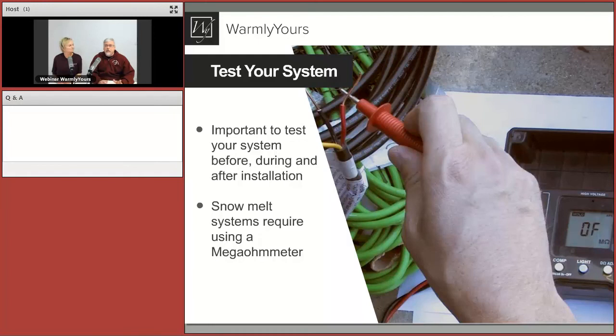This product requires a mega ohm meter for testing. It sends 500 or 1,000 volts down the wire to make sure the insulation is intact on the three wires — red, yellow, and black — that keep them from touching inside the cable. A normal volt meter only has nine volts and can't do this. If someone smashes those wires together with a jackhammer or shovel, you could have a short. That's why this testing needs to be done by a licensed and bonded electrician.